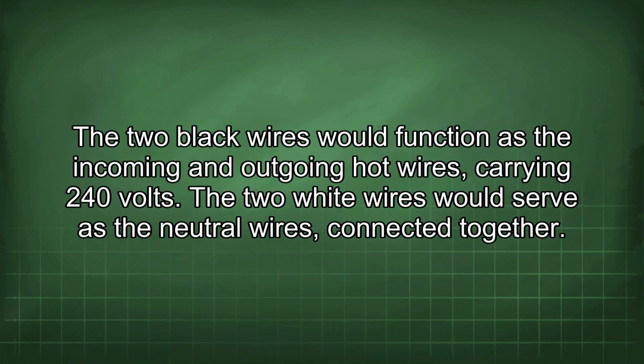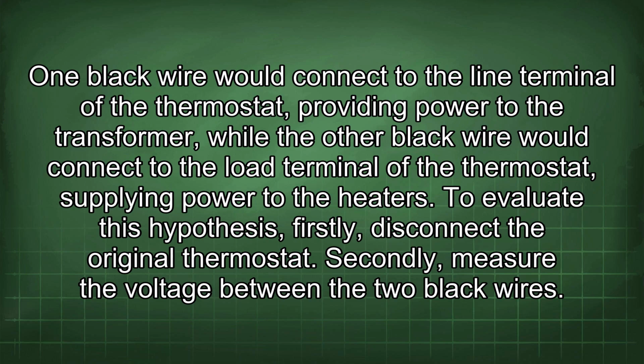The two black wires would function as the incoming and outgoing hot wires carrying 240 volts. The two white wires would serve as the neutral wires connected together. One black wire would connect to the line terminal of the thermostat, providing power to the transformer, while the other black wire would connect to the load terminal of the thermostat, supplying power to the heaters.